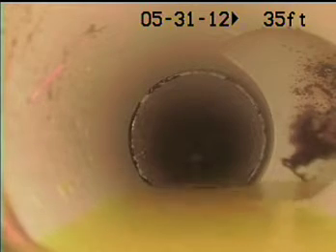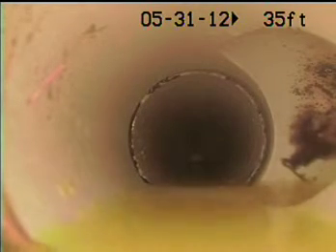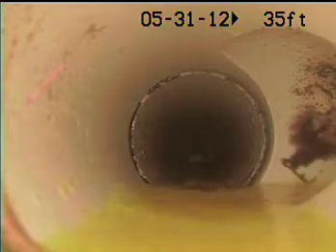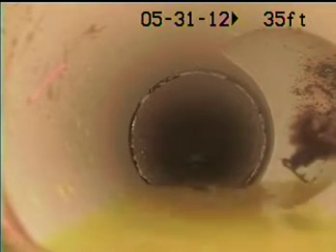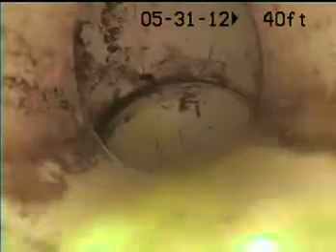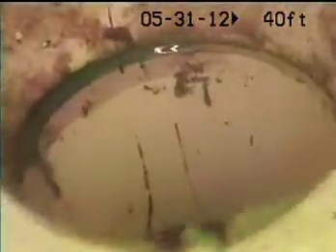So at 35 feet, we have a line tying in. This is where exam room 5 and 4 tie in. It just had to turn green when we went past it. Go back up to that main clean out. Believe this to be the main clean out at 41 feet. We're going to pause the video here and verify. Okay, we verified this is the main clean out. Pulled the cap and I can see the camera head hanging down this riser.